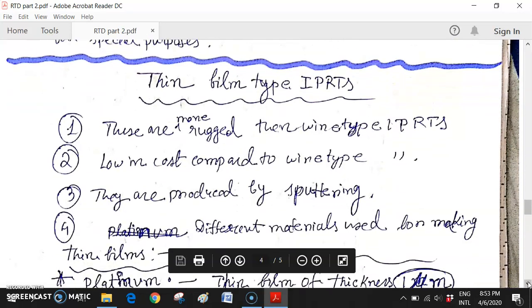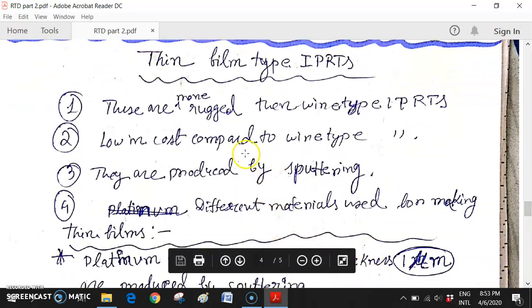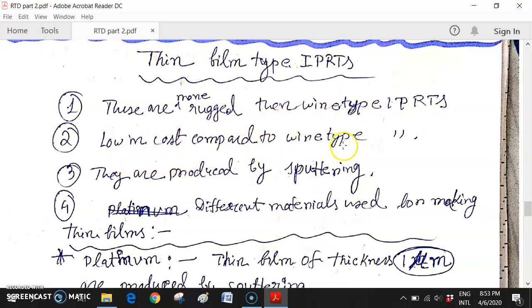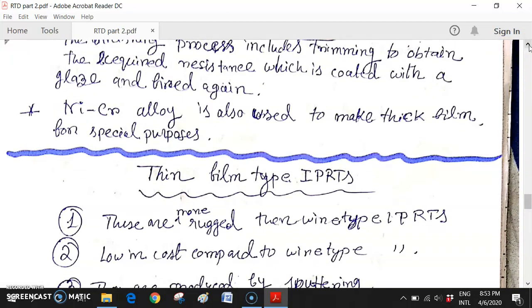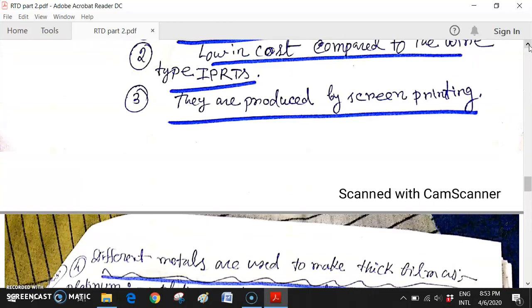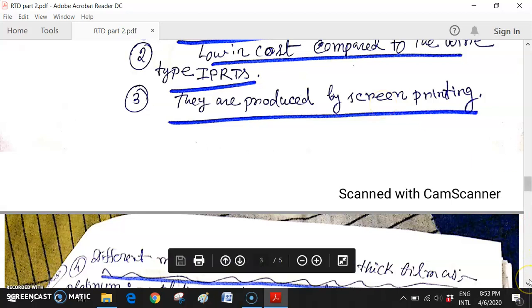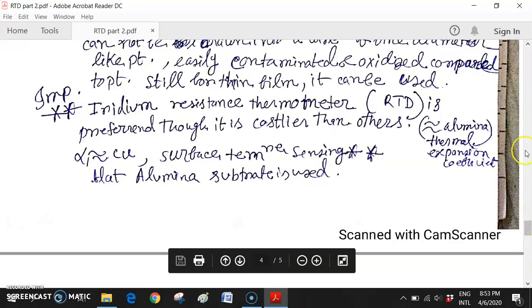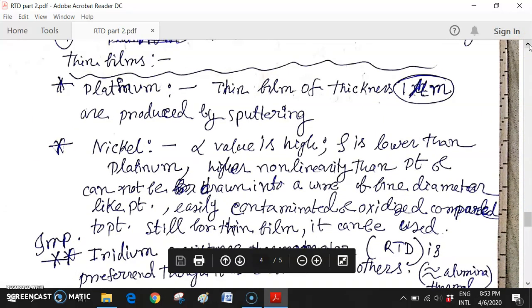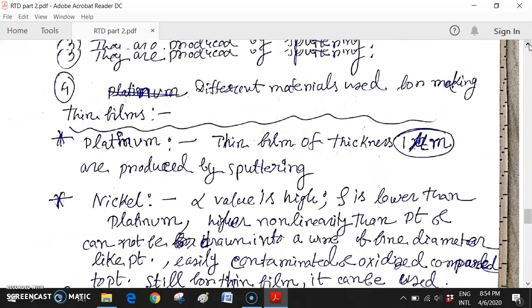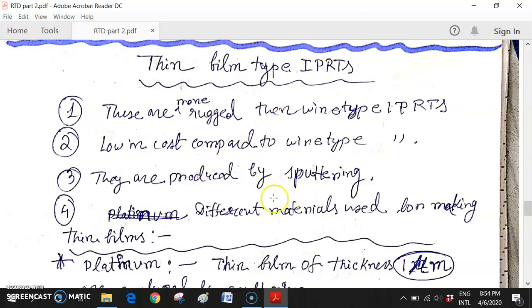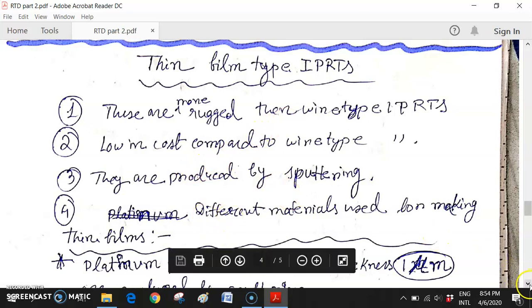For thin film type IPRT, they are more rugged than wire type IPRT and lower in cost compared to wire type. The key difference is that thick film is produced by screen printing, whereas thin film is produced by sputtering. Different materials are once again used for making thin film IPRTs.